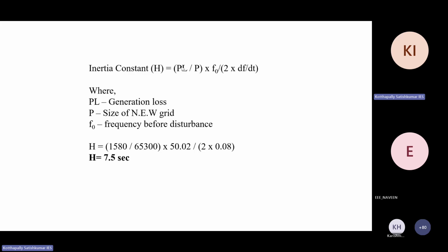If you substitute PL as 1580 MW, the loss of generation, divided by the size of the grid — the total connected generation of 65,300 MW — and the pre-disturbance frequency of 50.02, then multiply by 2 with the df/dt data, you get 7.5 seconds. This is the inertia constant of the Indian NEW grid at that time.